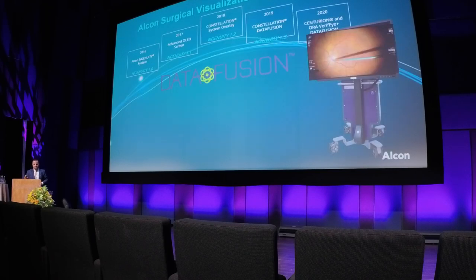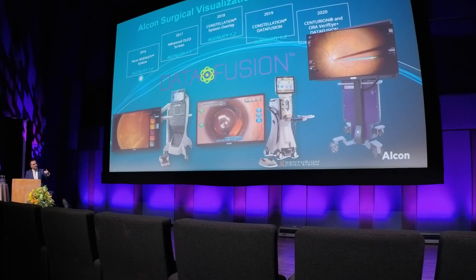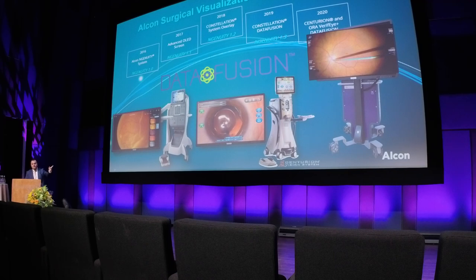Another important thing is the evolution of the system until version 1.4. First there was data fusion with Constellation; later, wireless data fusion and connection with the Centurion. Data fusion means we can control the NGENUITY color profiles and color channels through the pedal of Constellation or Centurion, and the link with Centurion is wireless — so less wires in the OR, which is important.